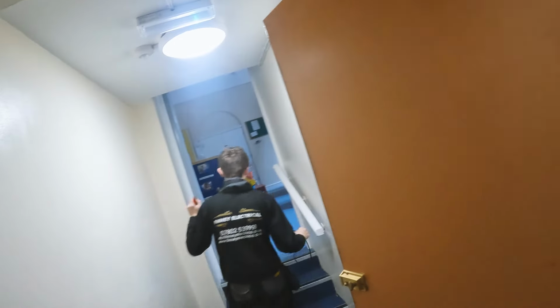We're still bad. It's still bad, is it? And then do your neutrals. So I've disconnected that bit of it. Right then, so the fault's still there. So now we can check the outgoings of those neutrals going to the lights, which is cool. So that would then tell us if that beam's fine, that beam's fine, that beam's fine, and then it'd eliminate them 6. So we'll keep chopping it off. Chop, chop, chop.